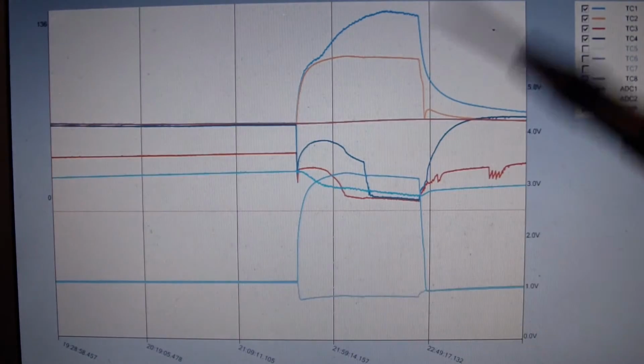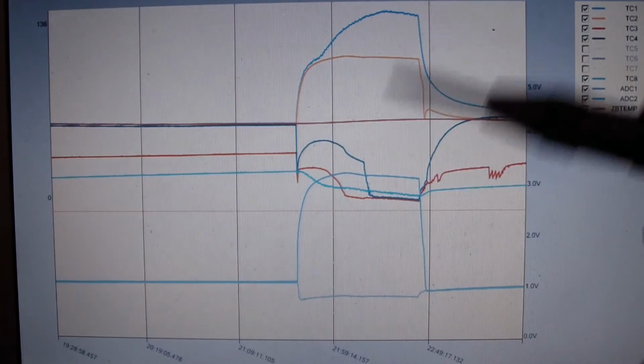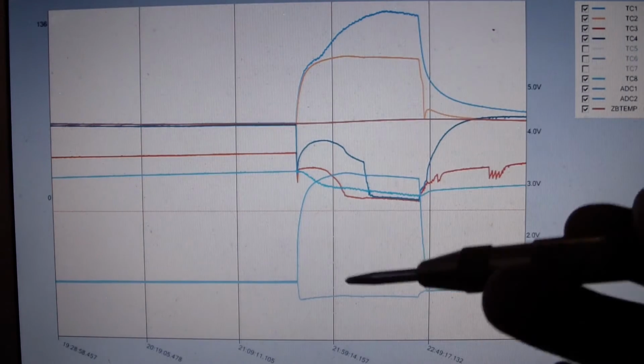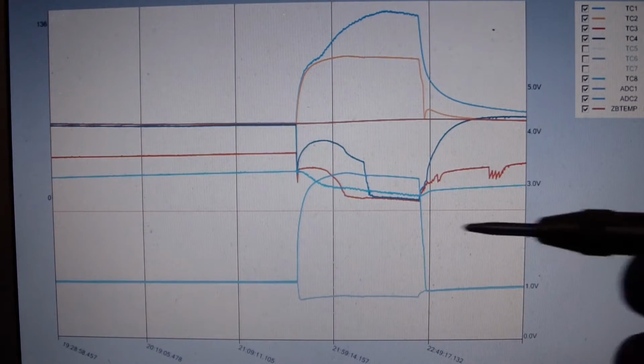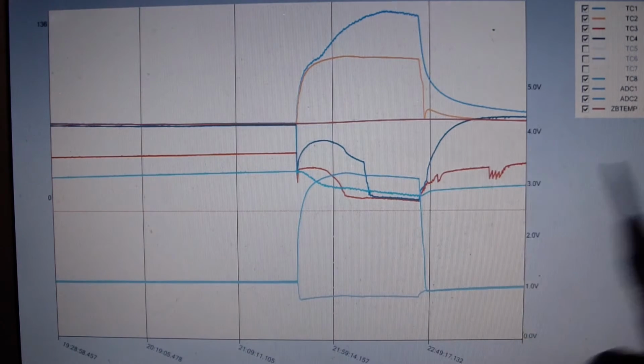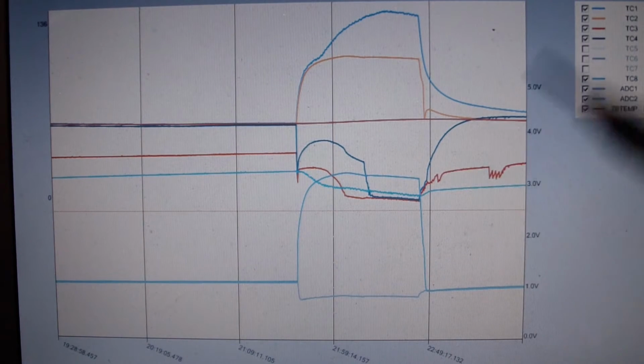So whenever the thermostat calls for cooling, right now it calls for it at 27 degrees with a thermocouple mounted to the bottom of the pan, and then it shuts off at 13 degrees. That seems to work relatively well right now, but I'll get that a little bit tighter here, figure out what an appropriate setting for that is.